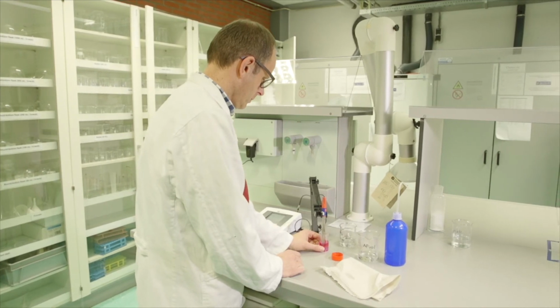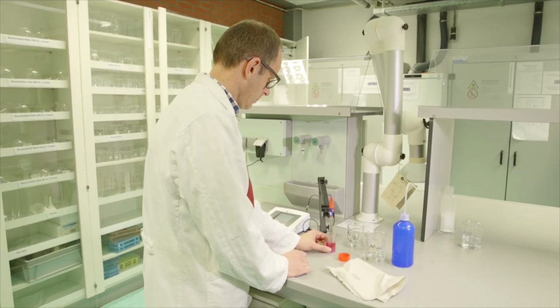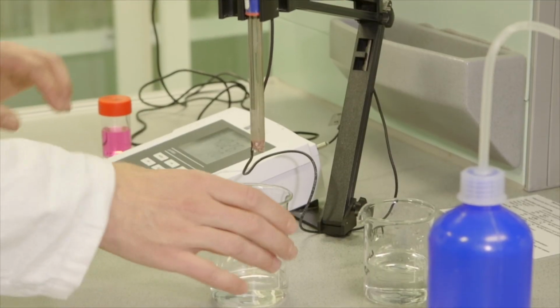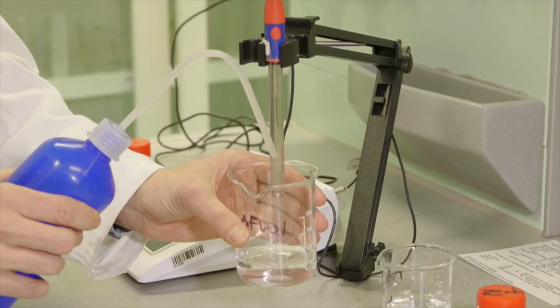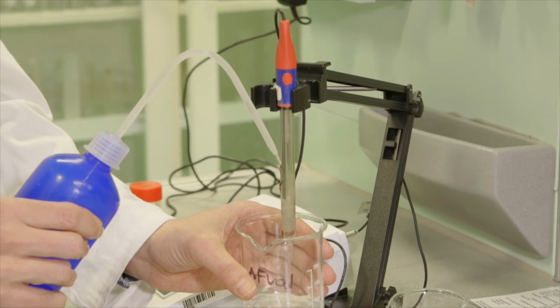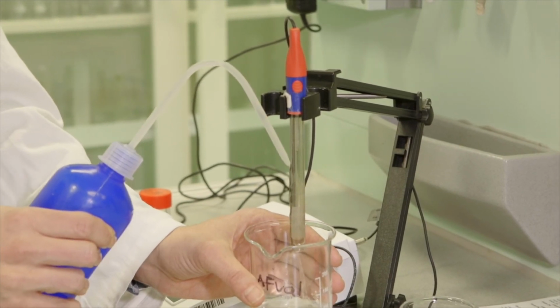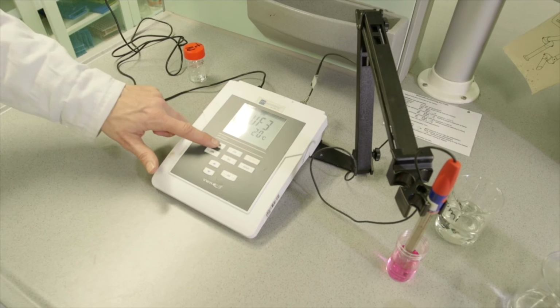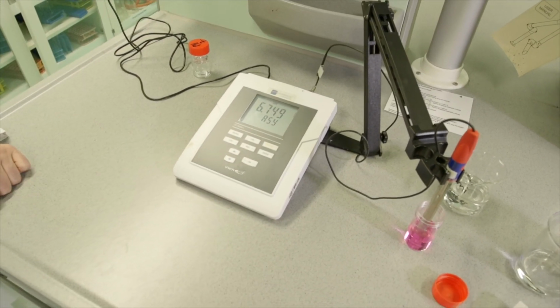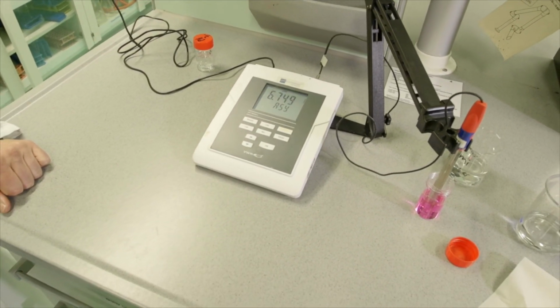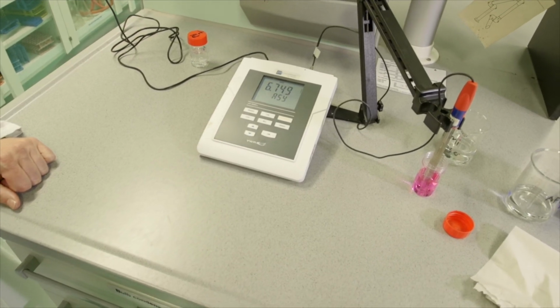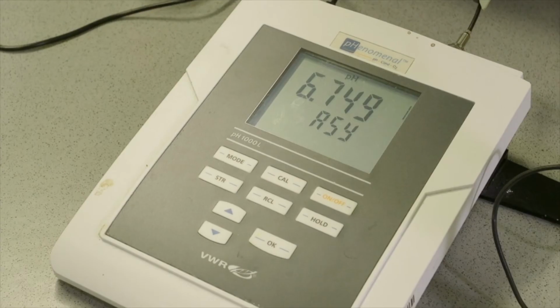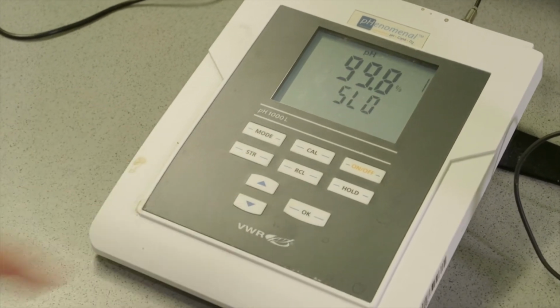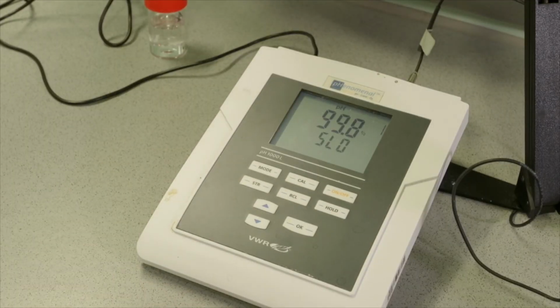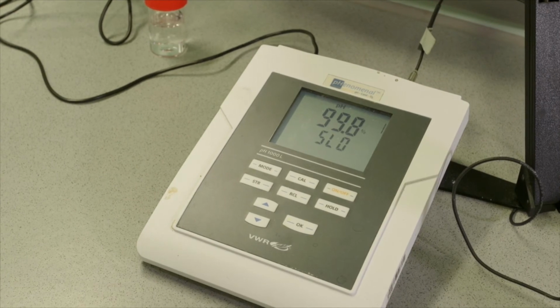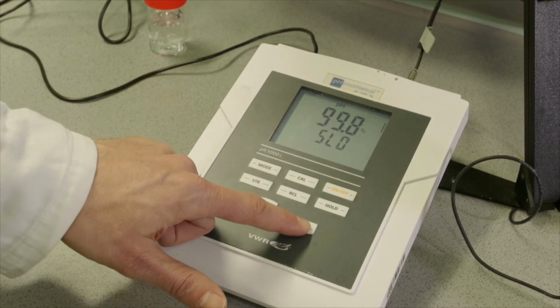When the calibration is completed, buff 3 appears on the display. Rinse your electrode off into the waste container and insert it into the beaker. We don't measure a third buffer and press the mode button. ASY appears in the display, which is the null point of the calibration line. Make a note of this in your lab journal. Press OK. SLO appears in the display and indicates the slope of the calibration line. Note this in your lab journal and then press OK.